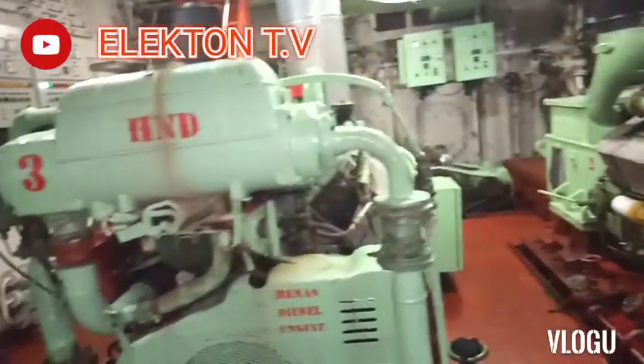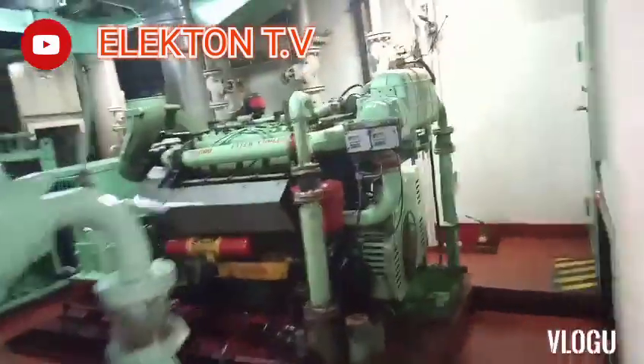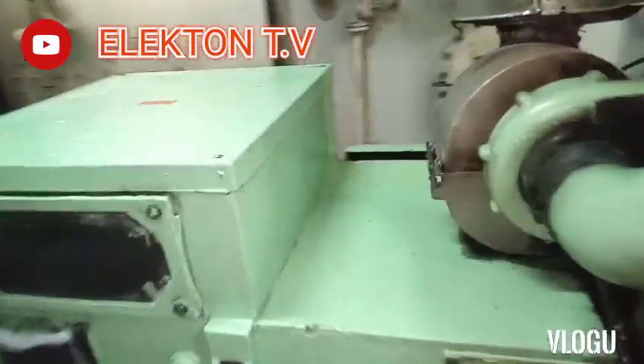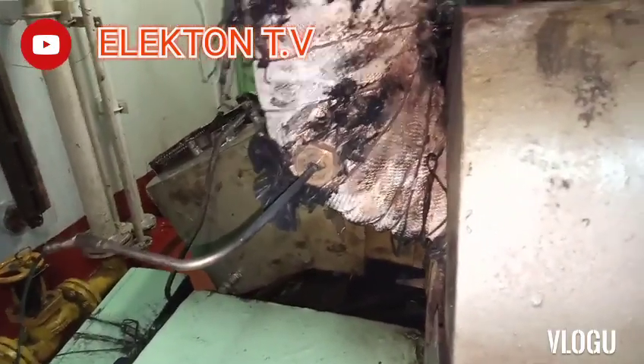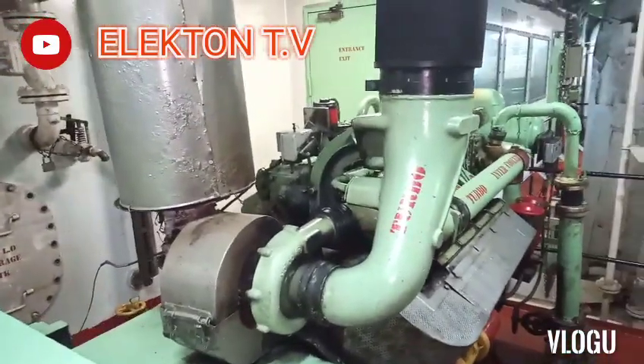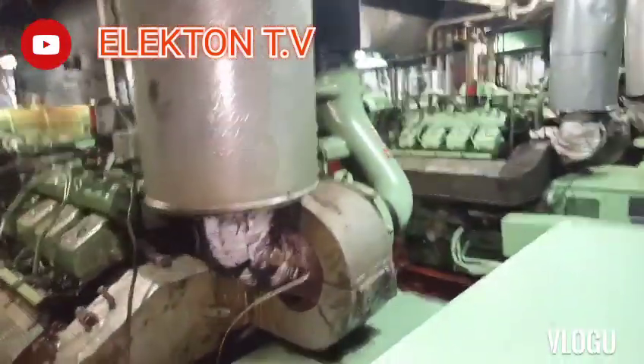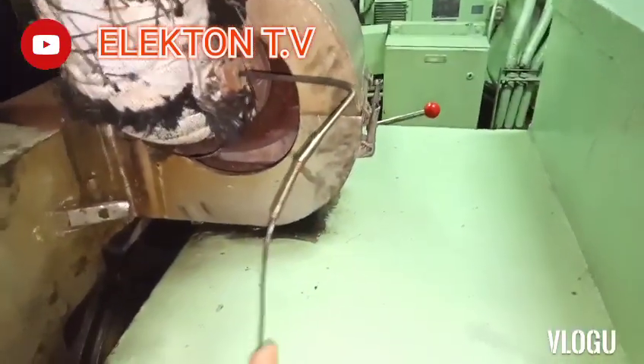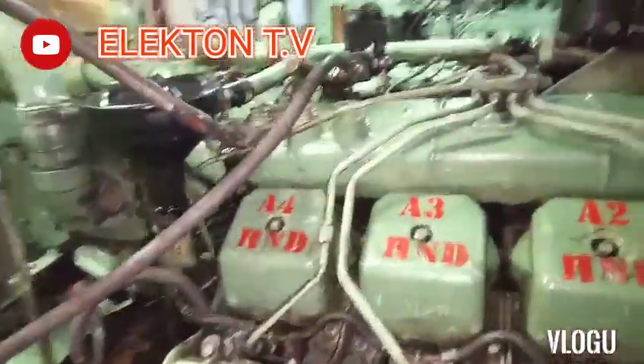Hello guys, welcome back to my YouTube channel Elekton TV. Today's knowledge sharing video is about exhaust temperature of a diesel generator. It's very high and not normal — the reading is almost 700 plus degrees Celsius. If we compare to other generators running normally, the reading is only 200 to 250 degrees Celsius.